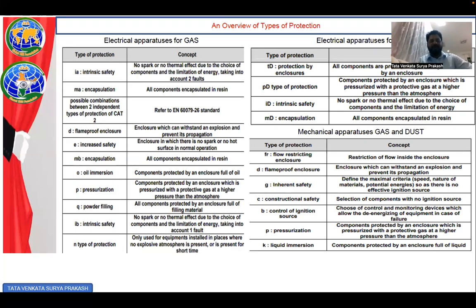That means no spark or thermal effect, due to the choice of components and the limitation of energy, taking into account two faults. That is based on routings and seal ratings. We will see that at no point in time will two faults happen simultaneously. So that should be designed for intrinsic safety.